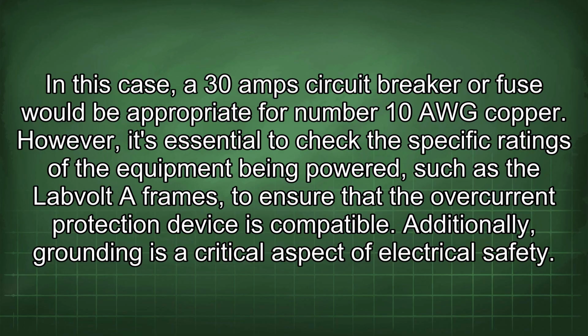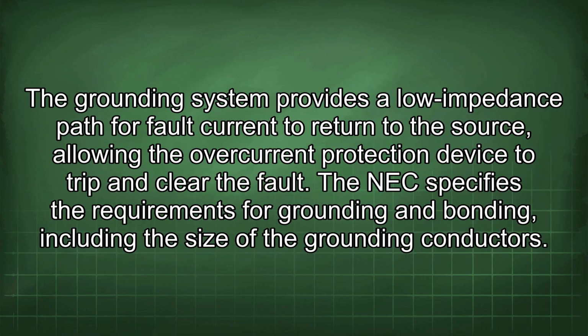However, it's essential to check the specific ratings of the equipment being powered, such as the Labvolt A frames, to ensure that the overcurrent protection device is compatible. Additionally, grounding is a critical aspect of electrical safety. The grounding system provides a low impedance path for fault current to return to the source, allowing the overcurrent protection device to trip and clear the fault.